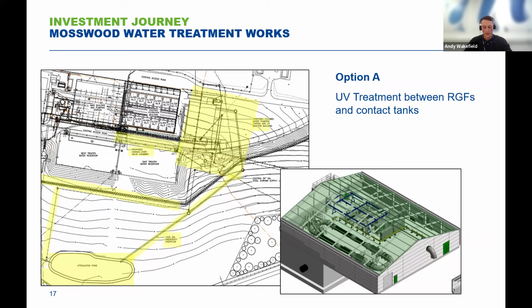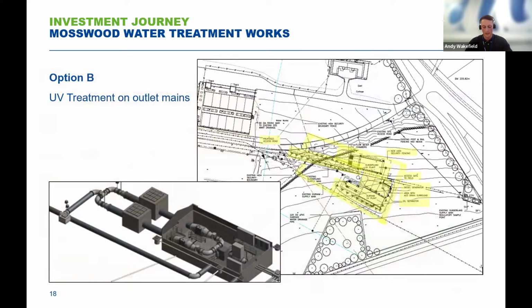The buildability and commissioning would have been very complex with a solution of this type. It would require new buildings on site, pipework reconfiguration, and total change to the hydraulics of the site. And we would also live with a considerable risk during maintenance of one of the reactors, as essentially the other reactor would act as a duty and standby system. There would be significant consequence for catastrophic failure as well on final water quality.